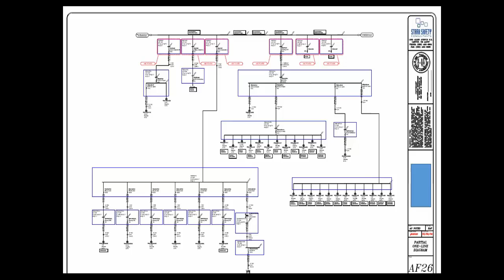Note that I didn't talk about system improvements during this process, because I'd clarify it's very difficult to include hazard mitigation and risk control pricing in a base RFP before the analysis has even been done. If you're trying to reduce hazards and risk and include that in pricing as a lump sum or line item before you can quantify what hazards exist, that's not a good formula in my opinion. Having some detail in the process, like unit pricing or budget pricing, is doable and makes more sense. But requiring it in your base price when there's a thousand pieces of equipment in the building - how do you know what problems exist until the analysis is completed?